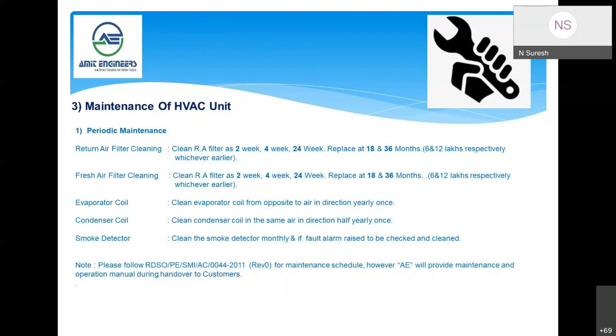Even though there is periodic maintenance, if there is a blockage in the filter for any reason, as briefed earlier, there are pressure differential switches that will give an indication to do maintenance, that is, cleaning.